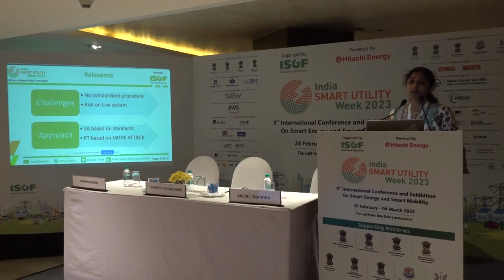For IEDs, you have IEEE 1686. You have separate standards for network switches. There's a whole standard that says what standards to refer to, which is IEEE C37.240. So you have a set of standards, and for any site engineer it will be very difficult to be comprehensive enough. That is one of the key challenges we have.